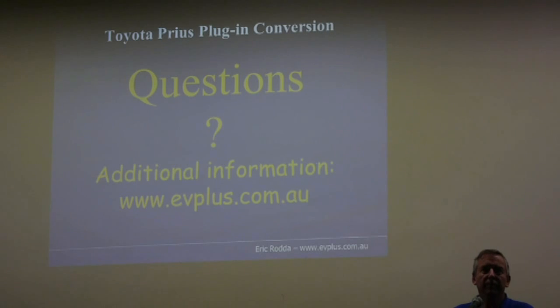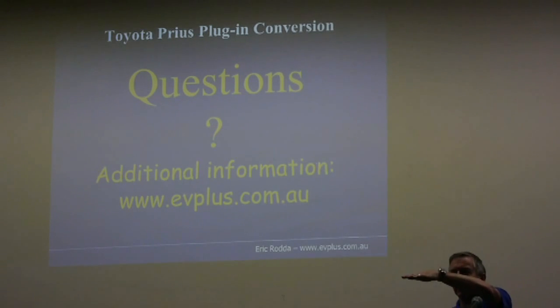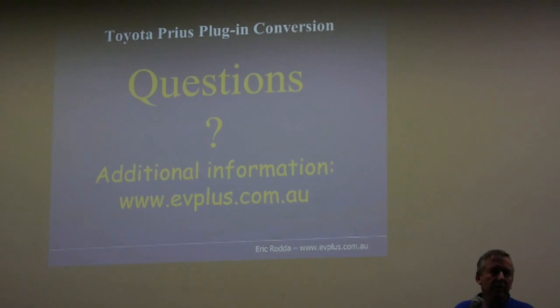No, it's not the second half. I should have brought it with me, I've got a curve of the actual charge. It's only the last 10 minutes it really tapers off on this particular one. It depends on your charger, but they tend to rise, and then the voltage starts rising rapidly, and in that rapid rise is where the current gets tapered off.